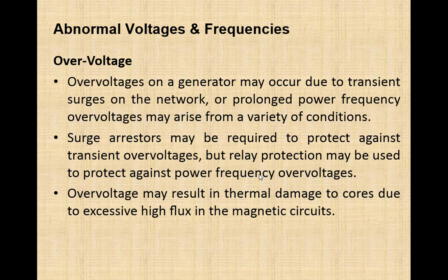What are the problems that may occur due to over voltages? Over voltage may result in thermal damage to the core due to excessive high flux in the magnetic circuit. Due to increase in voltage, flux produced in the core of the stator will also increase. That excessive increase in flux may result in saturation of core as well as heating in the core.